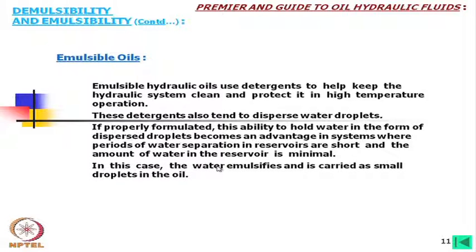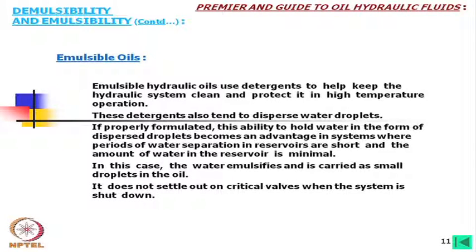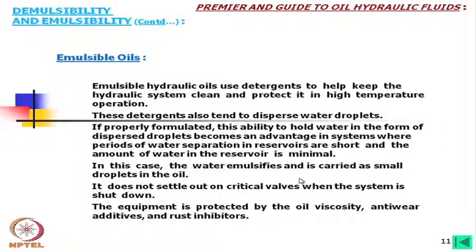Emulsible hydraulic oils use detergents to help keep the hydraulic system clean and protect it in high-temperature operations. These detergents also tend to disperse water droplets. If properly formulated, the ability to hold water as dispersed droplets becomes an advantage in systems where periods of water separation in reservoirs are short and the amount of water is minimal. The water emulsifies and is carried as small droplets in the oil; it does not settle out on critical valves when the system is shut down. The equipment is protected by the oil's viscosity, anti-wear, and rust inhibitors.